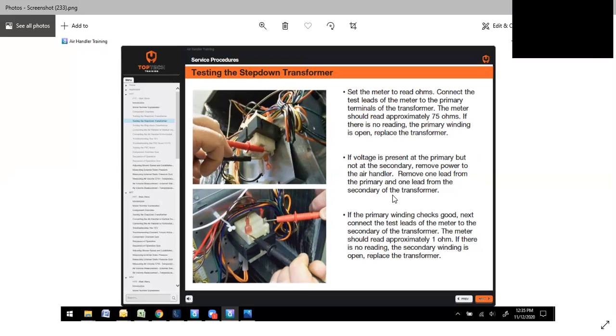If voltage is present at the primary but not at the secondary, remove power to the air handler, and remove one lead from the primary and one lead from the secondary of the transformer. If the primary winding checks out good, next connect the test leads of the meter to the secondary side of the transformer. The secondary side should read much lower, approximately 1 ohm or so. If you have approximately 1 ohm, your secondary is good. If there is no reading on the secondary, you have a bad secondary side of your transformer.